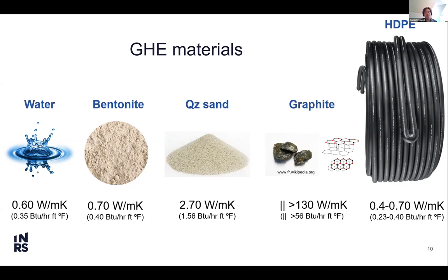And then the pipe that makes the heat exchanger is typically high density polyethylene. You see the thermal conductivity of this pipe is very low, 0.4 to 0.7 when it is enhanced with carbon-type nanoparticles, for a pipe that is specifically designed for geothermal heat pump systems, but most of the time it's just regular HDPE, 0.4 watt per meter Kelvin.